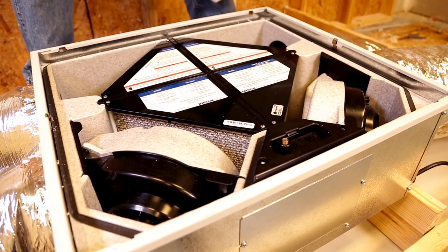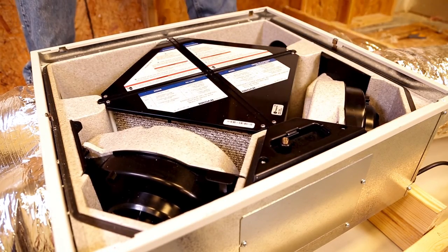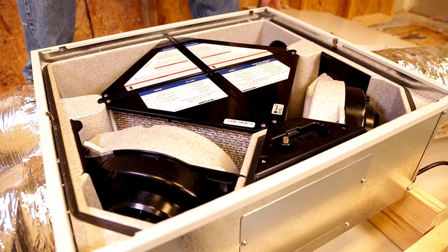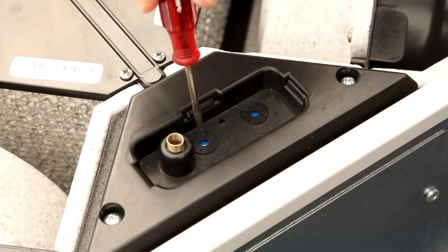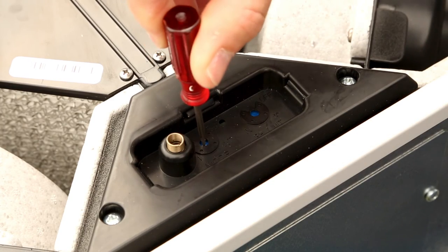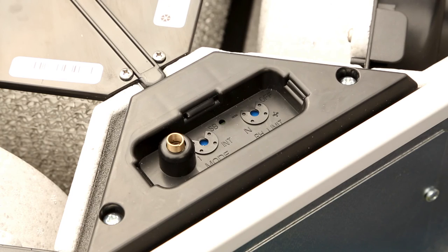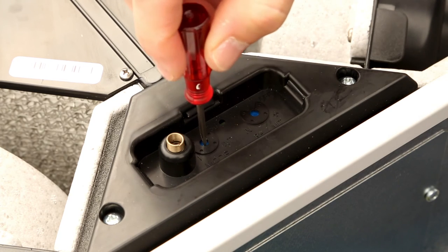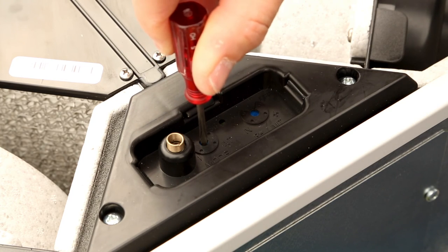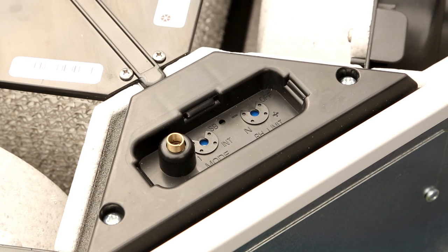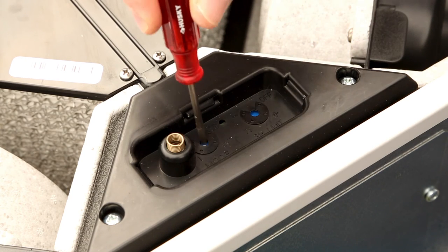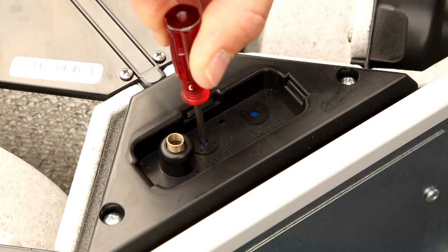Remove the door to access the mode and RH controls. The ERVS-100 features four available modes. In standby mode, the unit is off but can be activated in high speed by the 20-minute push button control if applicable. When the unit is in the intermittent mode, it works 20 minutes per hour in low speed and can be activated in high speed by the 20-minute push button control.